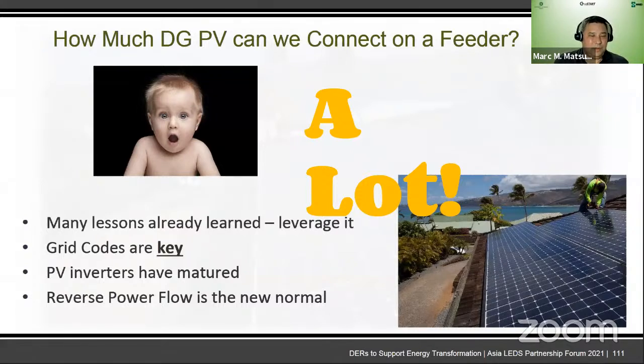As we moved forward, more and more kept getting connected, and more we had to connect. So the question was, how much can we keep connecting to these distribution feeders? What we've learned is that you can connect a lot, but the key is you need the right grid codes and connection requirements. You have to have inverters that are friendly with the grid, and you have to set up your grid for reverse power flow, because as growth continues, that's going to happen.